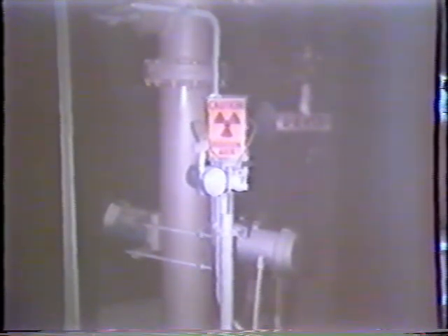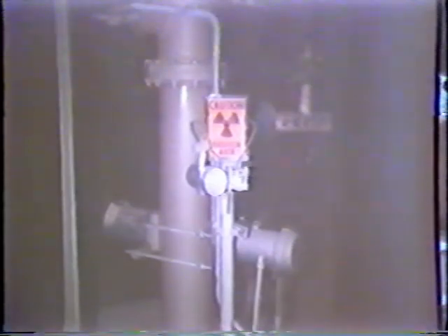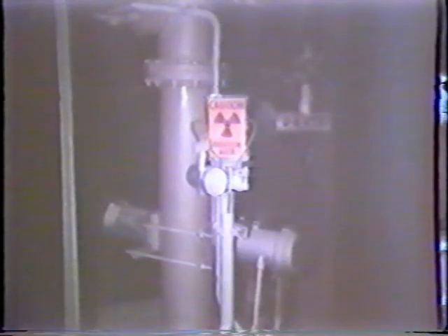Now, you know, the question comes up, just how necessary are the signs? Because, in fact, it's not really a radiation area at a foot away. They are designed for 2 mR per hour at a foot. Sure, right up against it, you may very well have a radiation area inside that foot. But the way the definition works is that an area within a foot is not considered exposure to the whole body. It would be considered what they call a hot spot.